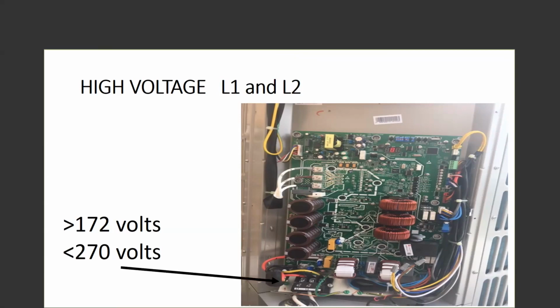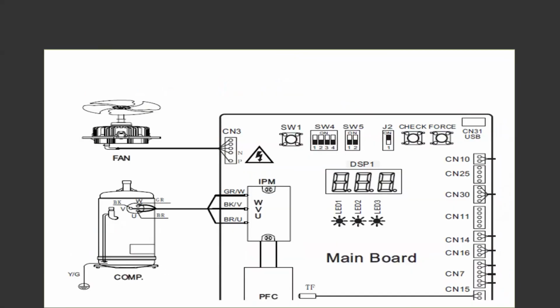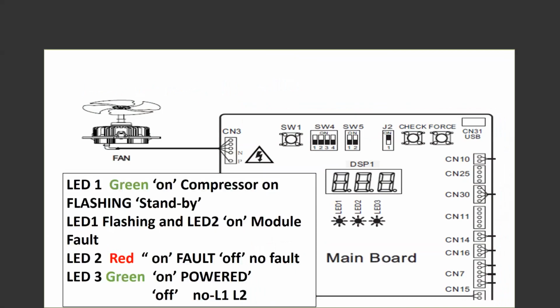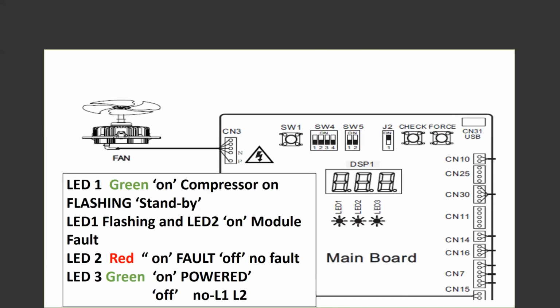Hooking it up on the bottom left-hand side, L1, L2. This is my board inside the unit. We know that we had those lights. Those lights mean something. You call me on a Friday afternoon, we're going to talk about those green lights, because the green light on the left-hand side is my green light showing me power. So that particular light will either flash or it will be solid. It tells me that we have L1 and L2, but we're also in a standby mode. The standby mode is nothing more than maybe we have disconnected the power, brought the power back on, and we're waiting for that particular 5.5 minutes on the 2.0 unit to regain what we need to make this system work. So again, standby or on.